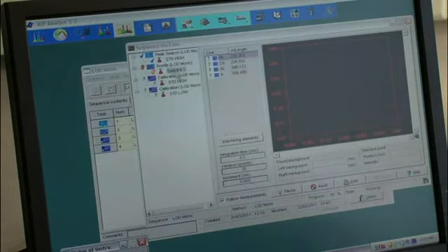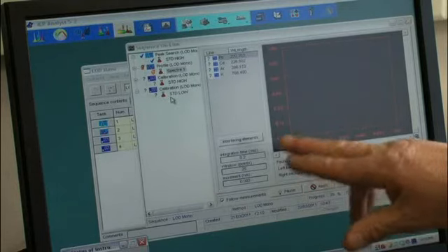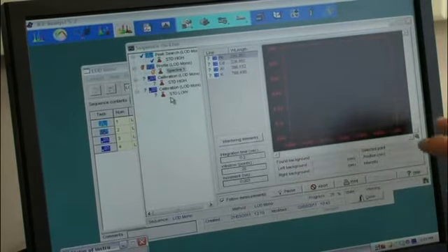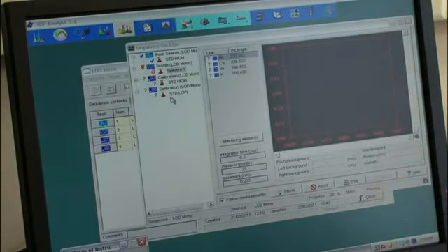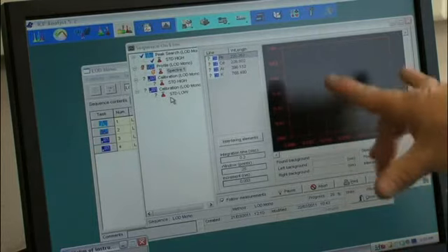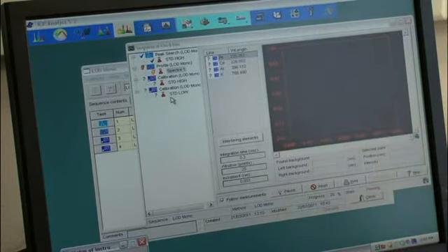So what I added to this sequence is a profile, and what that does is it records the peak search graph and it keeps it in your method. And what you can do with that is add background correction, which will subtract the background from each one of the calibrations and analysis. If you have a high background, you don't want that intensity in there.